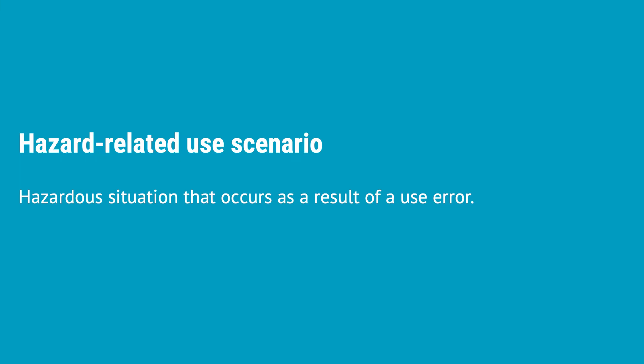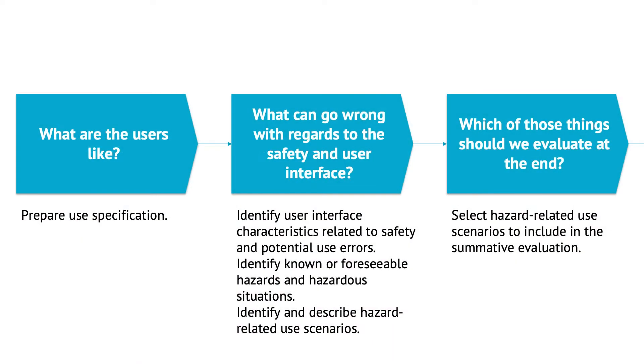Hazard-related use scenarios are the things you need to identify and document, because you will need them in the next step. Based on the identified use errors and what could go wrong, you decide which things to evaluate at the very end of your product development — identifying hazard-related use scenarios that will be included in your summative evaluation to ensure that your medical device is safe.